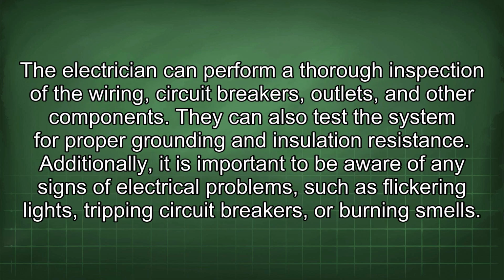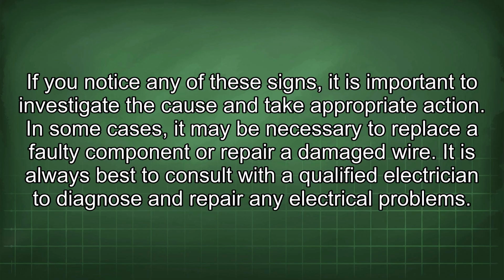The electrician can perform a thorough inspection of the wiring, circuit breakers, outlets, and other components. They can also test the system for proper grounding and insulation resistance. Additionally, it is important to be aware of any signs of electrical problems such as flickering lights, tripping circuit breakers, or burning smells. If you notice any of these signs, it is important to investigate the cause and take appropriate action. In some cases, it may be necessary to replace a faulty component or repair a damaged wire. It is always best to consult with a qualified electrician to diagnose and repair any electrical problems.